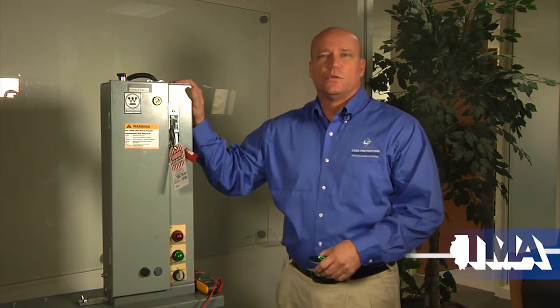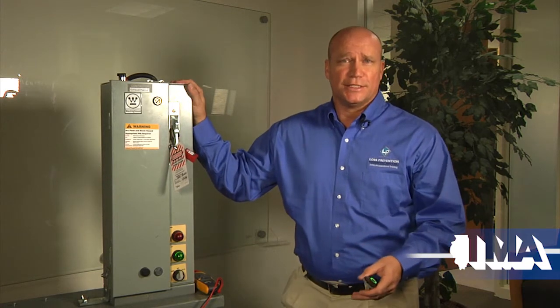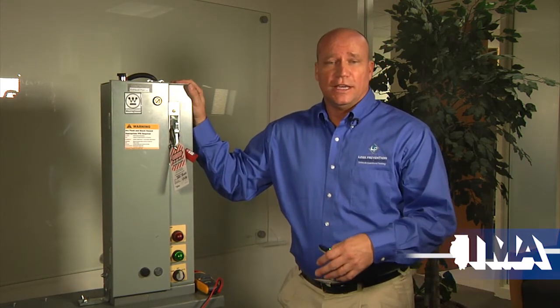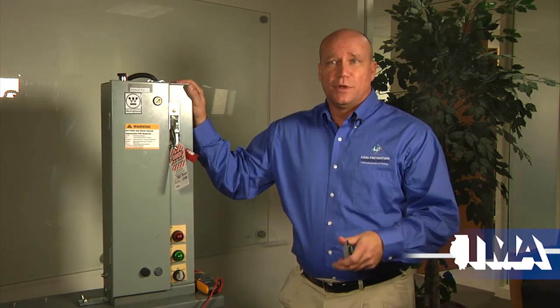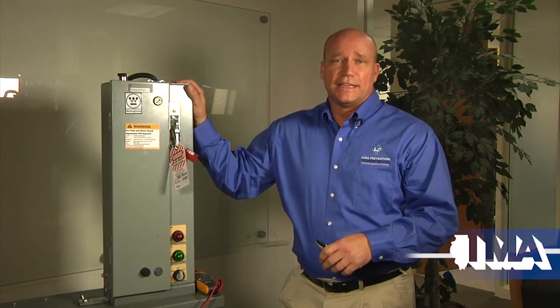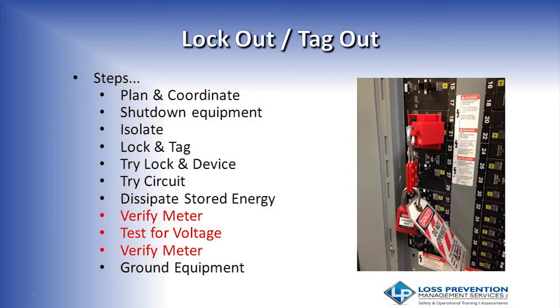So most of the work that you're probably going to be doing is on de-energized equipment, which you're going to be locking out and verifying de-energized. That's one of the primary and most important steps of the lockout tagout process when you're dealing with electrical equipment. The other steps that you may see here are isolation: how to safely isolate this, how to safely switch to make sure you're doing it just in case something were to blow up. Anytime you make and break electrical connections, there is a possibility. Also, how to test and apply locks. That's not part of this presentation because we don't have a lot of time for that, but it is an important aspect of the lockout tagout process.